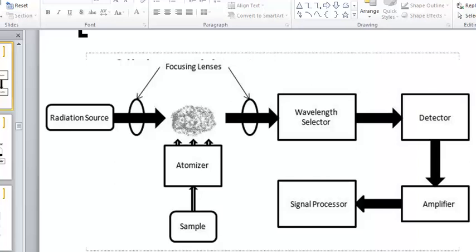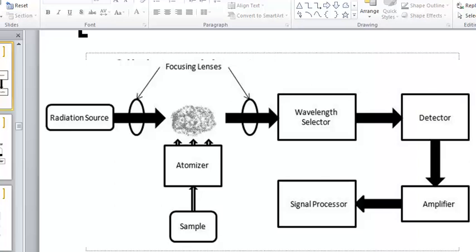The wavelength selector, this is what we're calling the monochromator. And the monochromator takes that specific wavelength, and it makes sure that only that one wavelength makes it to the detector. It doesn't want any outside interferences. It doesn't want anything to disturb the detector while it does its job. And that's the purpose of the monochromator and the grating that's on the inside. The monochromator then allows the light to escape, which is cleaned up, and that eventually goes to the detector.